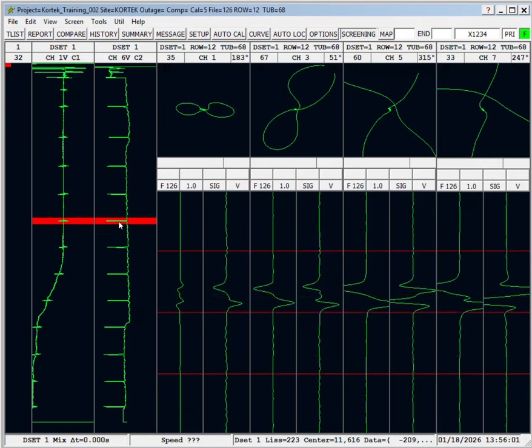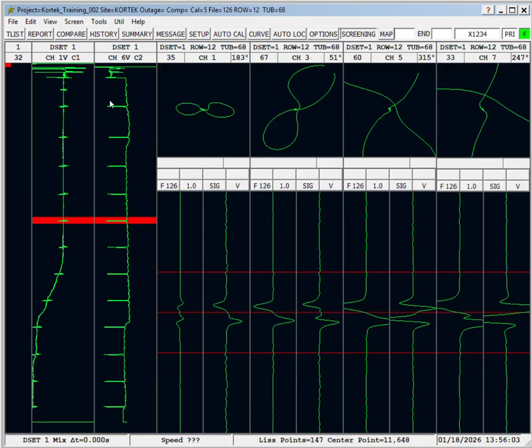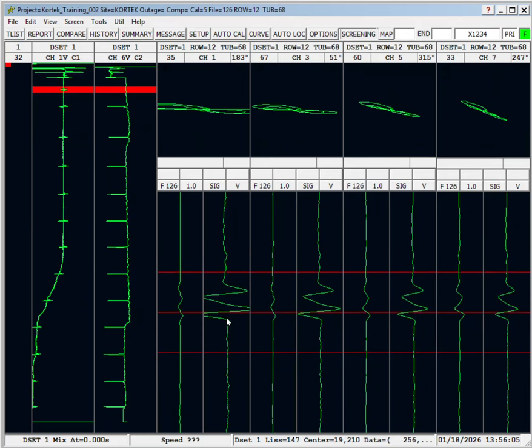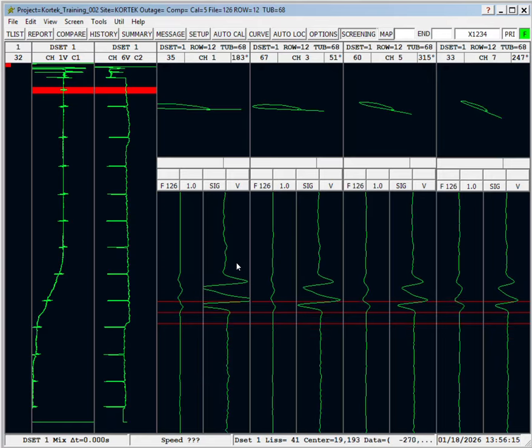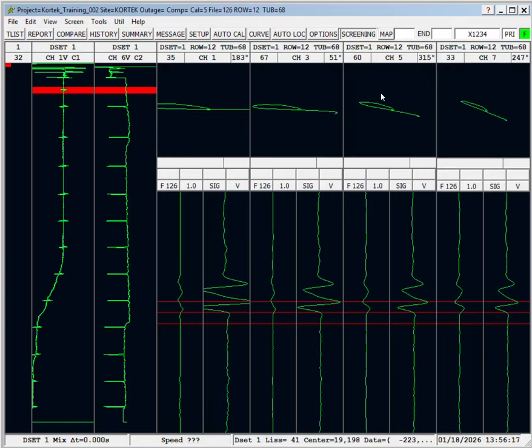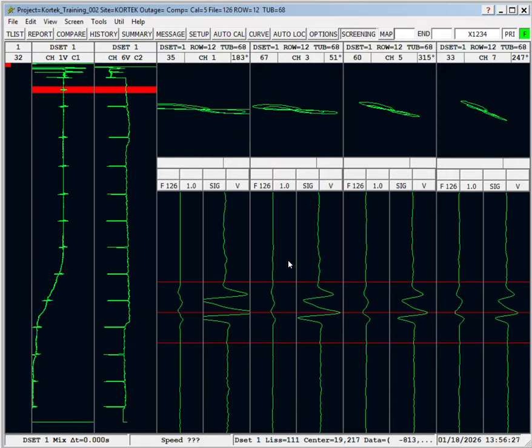So it's very important that every time you see a dent signal like that, you want to look for counterclockwise rotation of the different differential channels. Once they start to rotate counterclockwise a bit, especially on the lower channels like channel 5, that's when it's a suspect that you might have some degradation at the same location of the dent.